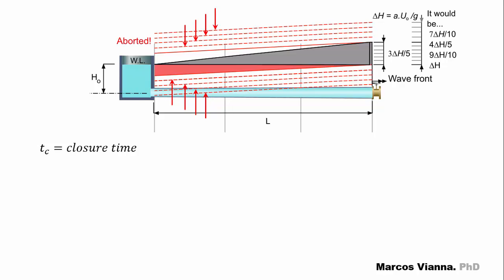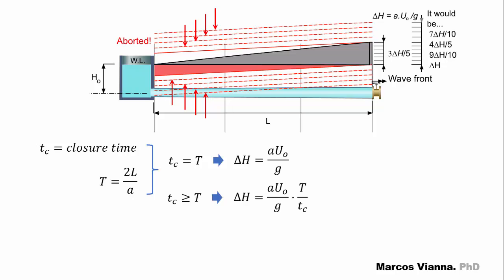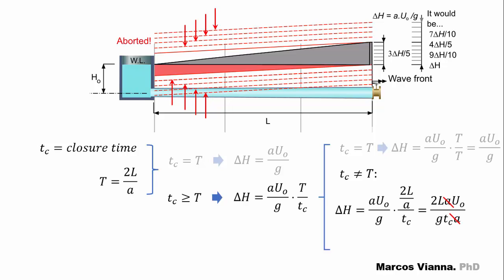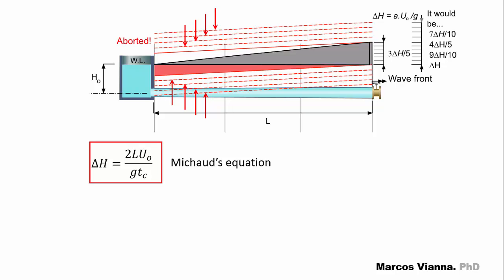We can find a formula for this value. Let TC be the closure time, and T equals 2L over A be the reflection time. As we saw in the quick closure video, when TC equals T, we have delta H equals AU0 over G. When TC is greater than T, delta H will be proportionally smaller. If TC equals T, delta H will be AU0 over G, as it should be. If TC is not equal to T, we substitute the values and find that delta H equals 2LU0 over GTC. This expression is known as Michaud's equation, and it fits our case.